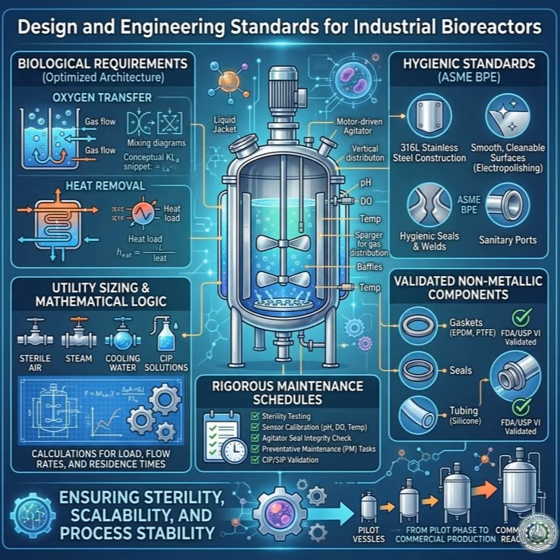Here's where it gets really interesting for me. We talk so much about the 316L stainless steel. It gets all the glory. But steel doesn't bend. To connect two pipes or seal a glass viewing window, you need flexible seals. The unsung heroes of the bioreactor are the non-metallic parts. Oh, absolutely. The elastomers and polymers, they hold the fortress together. Yes, the gaskets, the O-rings, the valve diaphragms. The source explicitly states that these are made of highly advanced materials. We're talking about PTFE, which most people know as Teflon, or heavy-duty synthetic rubbers like EPDM, FKM, and high-grade silicone. Right. And the crucial takeaway here is that you cannot just use whatever standard gasket the vendor ships by default.